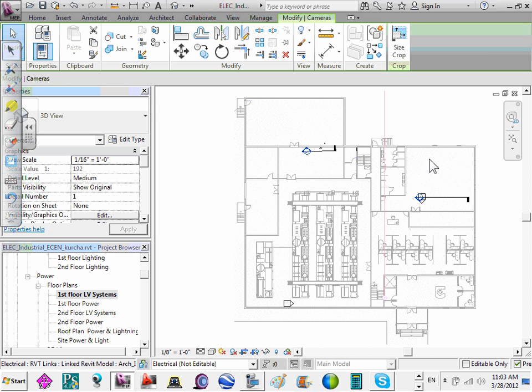Pull stations are not required by code anymore. So if there was no sprinkler system in this building, you're going to have a pull station at each exit and on each level, so it'd be on the second level of the stairwells. If this was a high-rise building, you're looking at smoke detection in each stairwell for stairwell exhaust and stairwell pressurization, but that gets into a whole different sequence, and you've got a sequence of operations. You've got to design the system, opening and closing dampers as we go. One thing to note: any fire smoke dampers that come up through the mechanical have to be controlled by the fire alarm system. So that's either putting a duct smoke detector on it and a control module and a relay on each fire smoke damper.